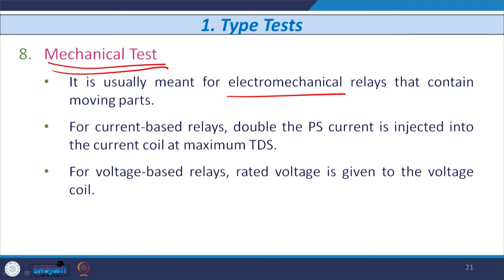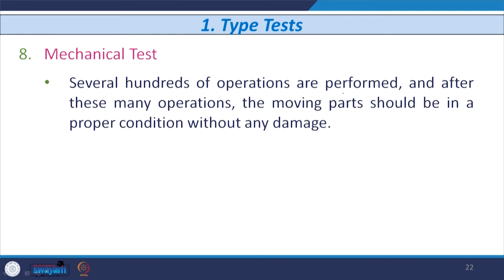For a current based electromechanical relay, double the plug setting current is injected into the current coil at maximum TDS, that is TDS equal to 1, and for a voltage based relay the rated voltage is given to the voltage coil of the relay. Several operations are performed, and after so many operations the moving parts should be in proper condition without any damage. There should be no damage on any of the moving parts of the relay, and this needs to be noted. This is how the mechanical test is performed on the moving parts of the electromechanical relay. So, this is all about the type tests that are to be performed by the manufacturer on the relay.